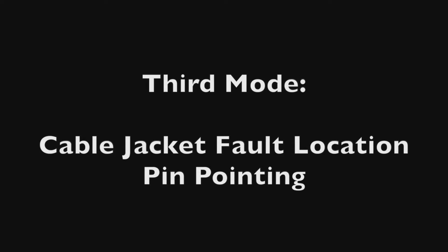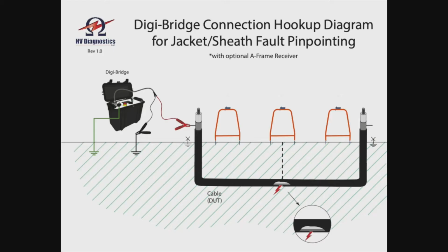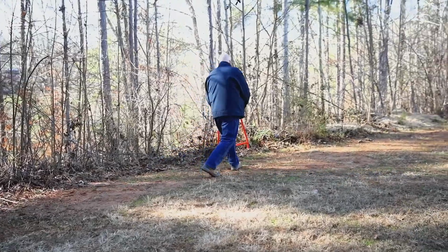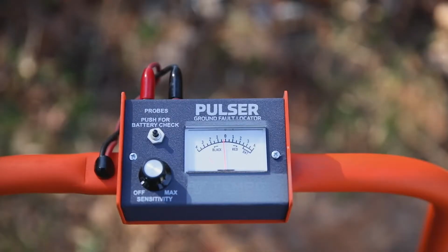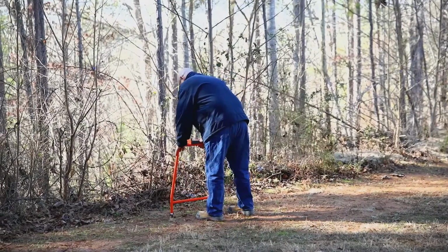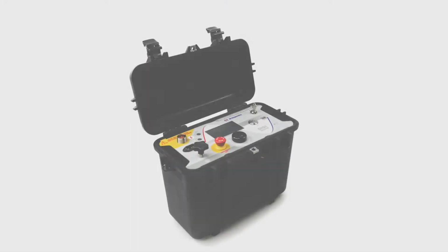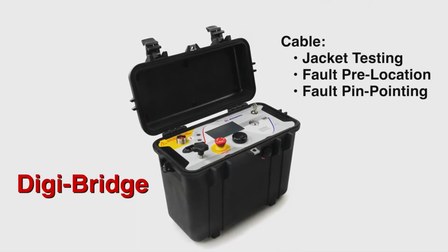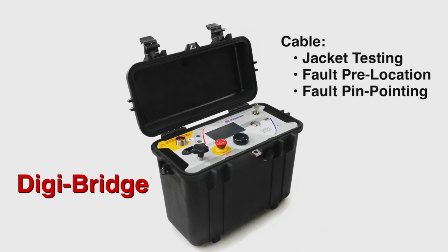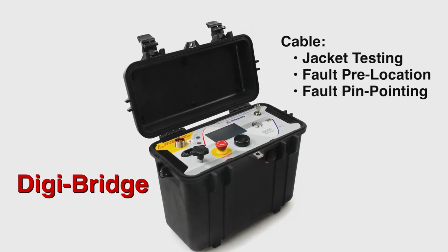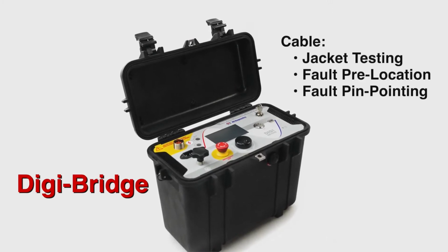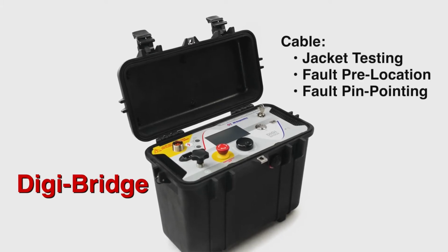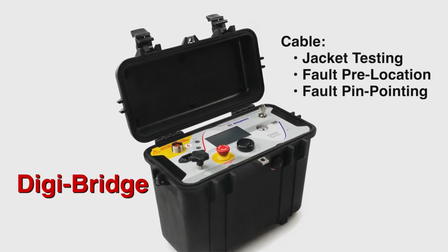Finally, the third mode is a cable jacket fault location pinpointing mode. For direct buried cables, the operator can then use the DigiBridge to locate the exact position of the fault in the cable using the optional A-frame receiver, using what we refer to as the voltage gradient method. All in all, the DigiBridge offers the user the ability to easily set up, test and locate cable jacket sheath faults. In addition, it is well suited to locate those hard to find cable insulation faults, particularly when other more traditional methods are limited or simply don't work.